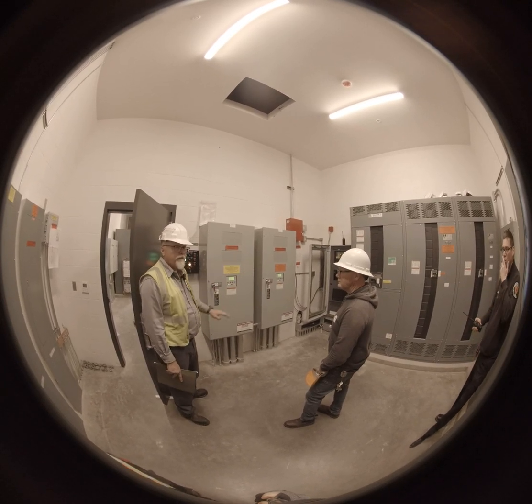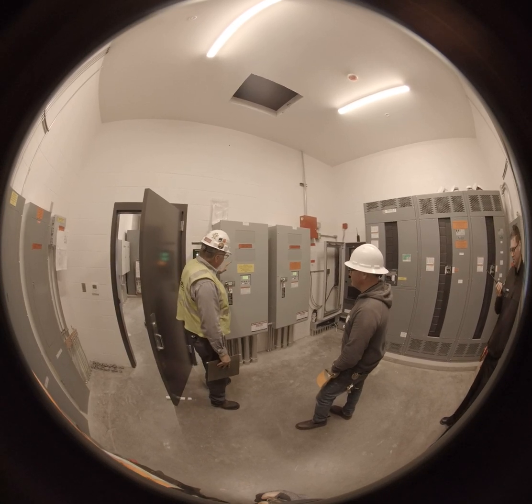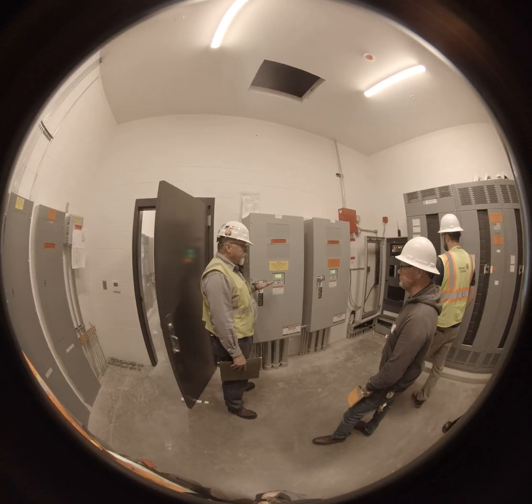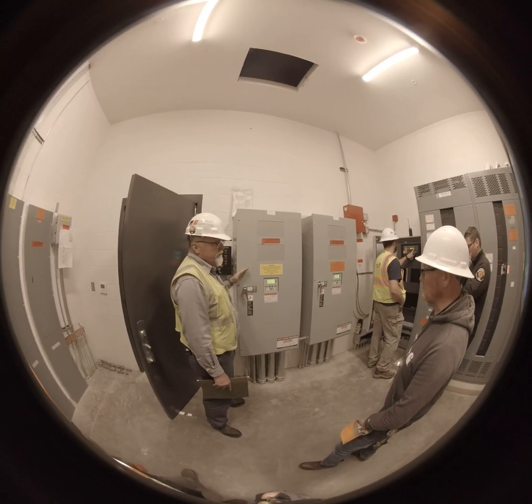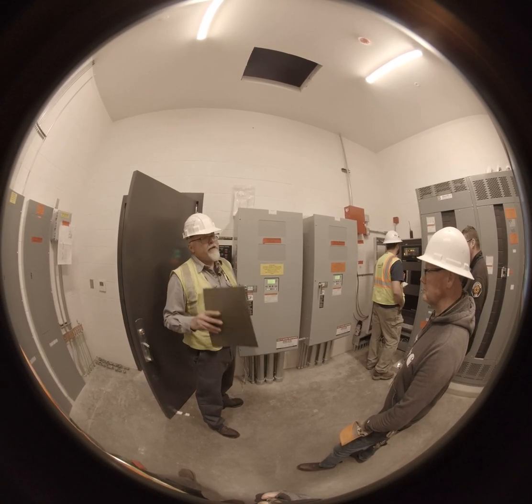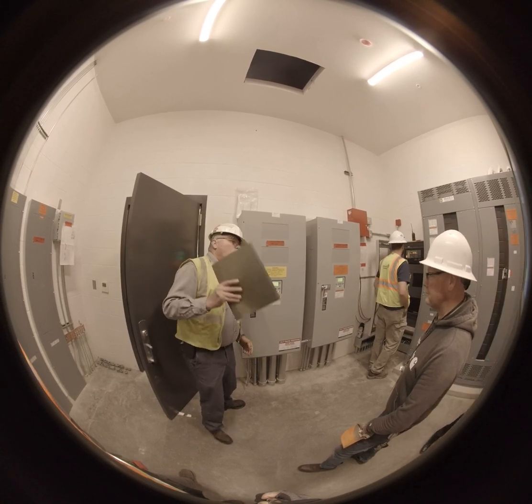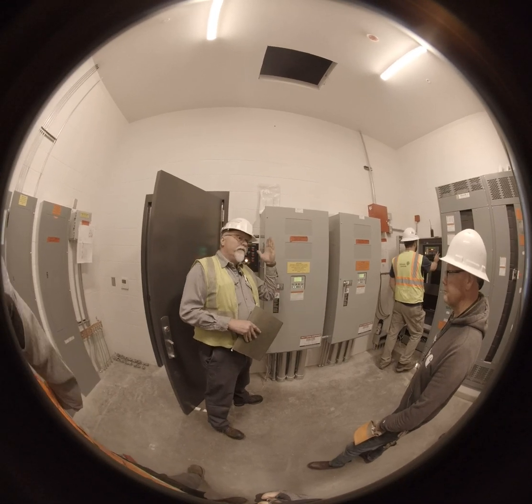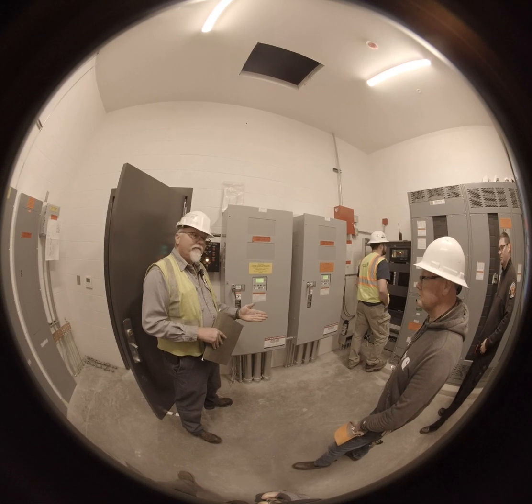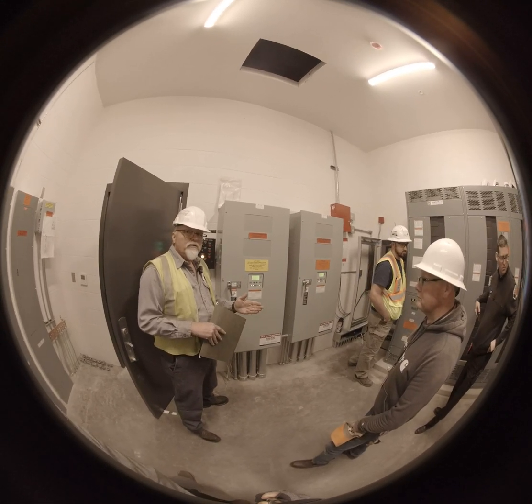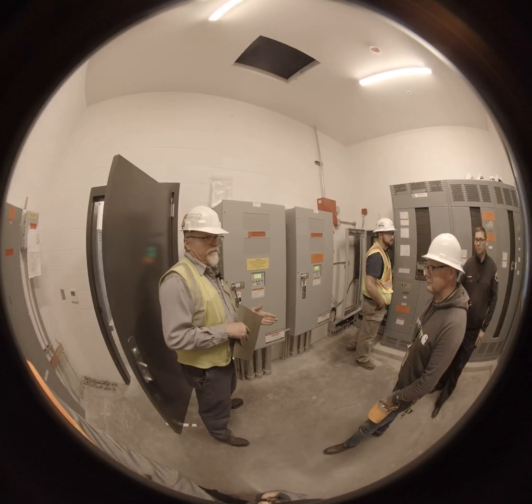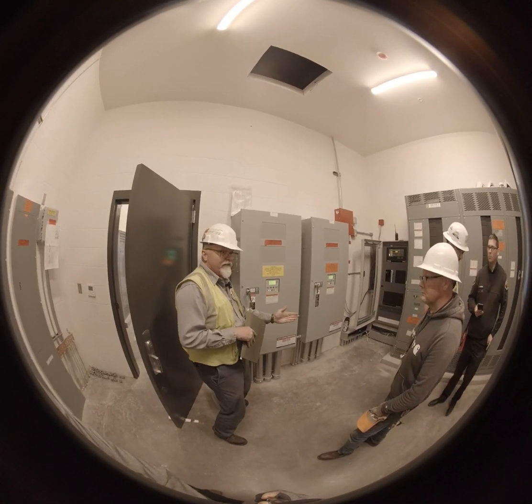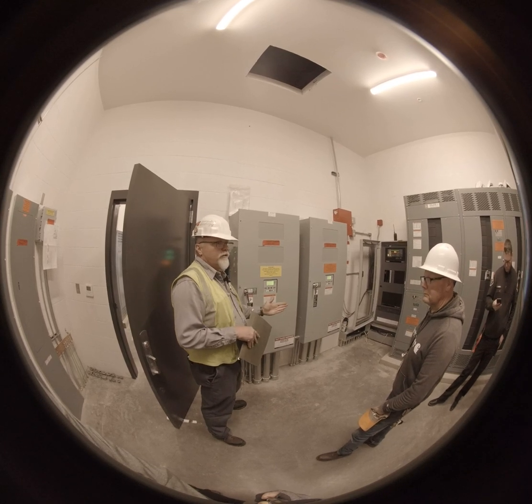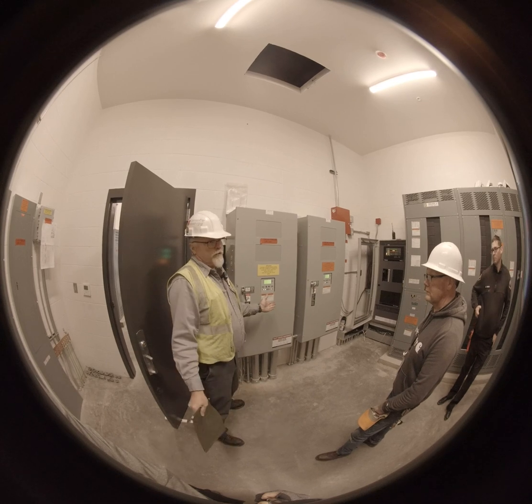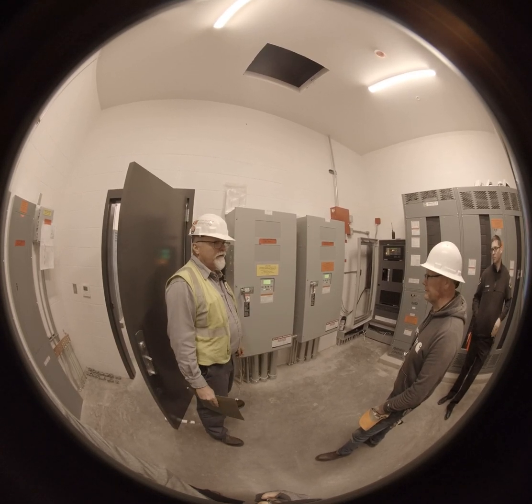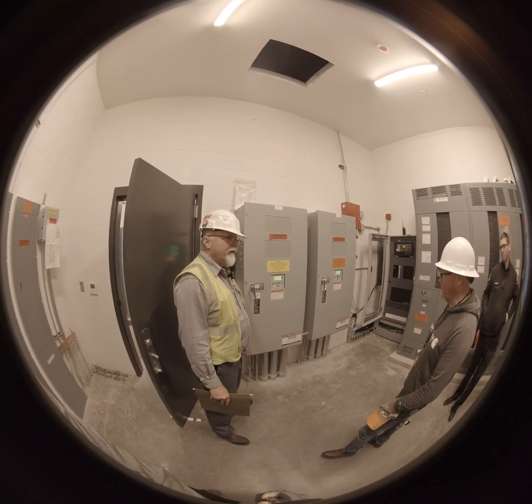Other than running, we're kind of done with the pounding around on it. Yeah, all good. Okay, so the control itself on these transfer switches is identical. They're both Group 5 ASCO controls. The difference is this one is set up with the elevator control in mind. So you hear how fast this transfer switch went over. If you have an elevator in motion and it transfers like that, it's going to basically freak people out. So what they do is a pre-signal. It will basically say, in 30 seconds or 90 seconds or whatever we have it programmed for, I'm going to transfer. So it will tell the elevator, okay, go down to a floor and open your doors. Then it'll transfer and then everything goes back to normal. That way you don't get people trapped in the elevator and issues like that.